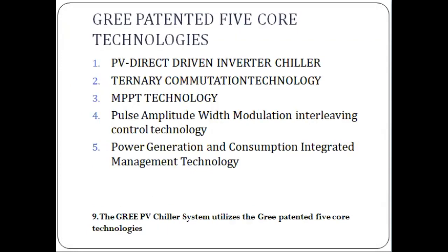Number 9, it utilizes the GREE patented 5 core technologies. In layman's terms, the use of an inverter chiller addresses part load performance and provides better efficiency for the central air conditioning system. Ternary commutation deals with switching technology between solar power and online grid connection of the chiller. MPPT technology pertains to power tracking of solar power generated by the PV system, as well as managing any unstable power delivery by the photovoltaic system. Items 4 and 5 focus on synchronized and parallel operation between two sources of power, the PV power and the online grid power.